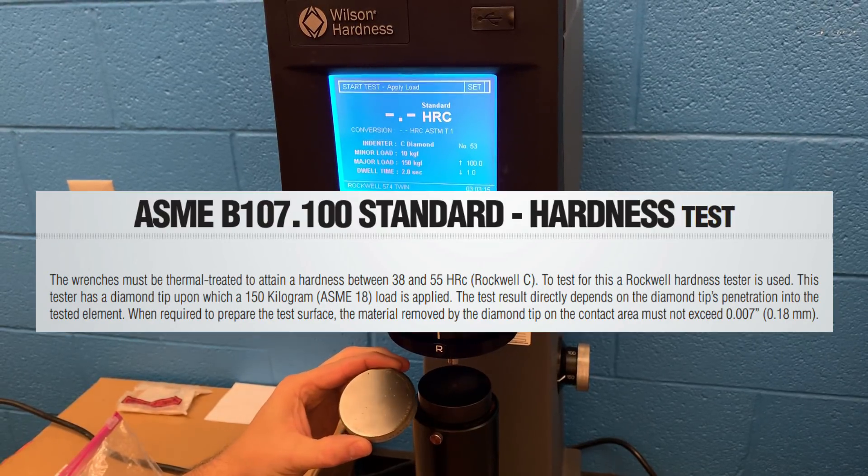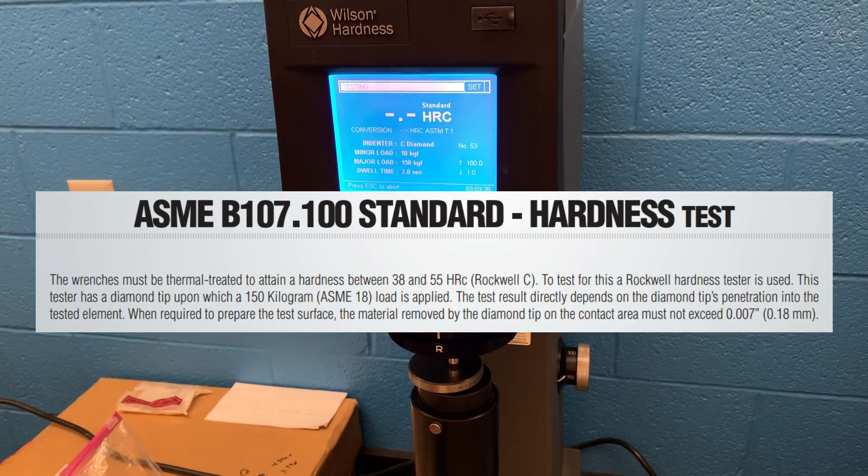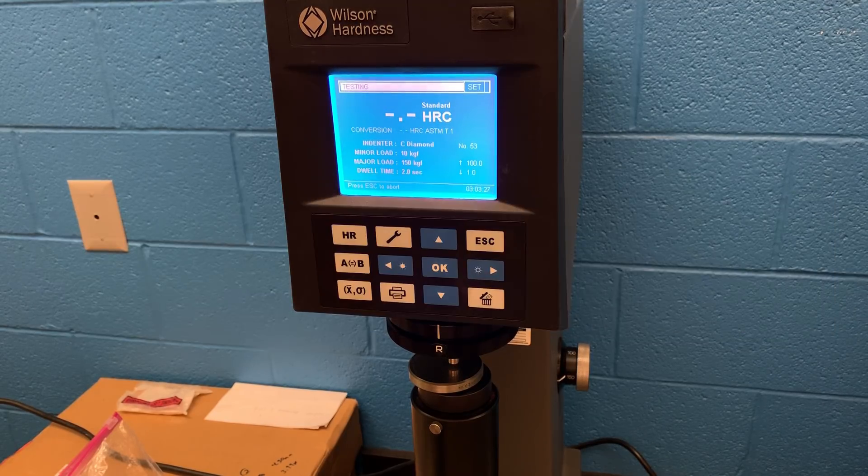Today we will be testing to ASME B107.100 standards. On the low side of calibration, we'll be trying to hit 31.1 and we ended up at 30.1. On the high side, we'll be trying to hit 61.8 and we hit 61.5. So we are within one HRC plus or minus when it comes to calibration.